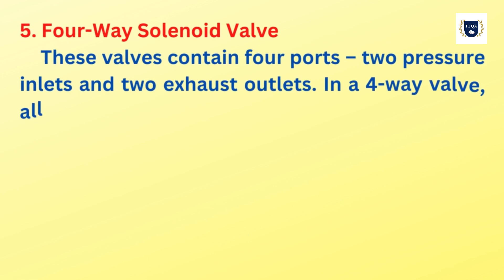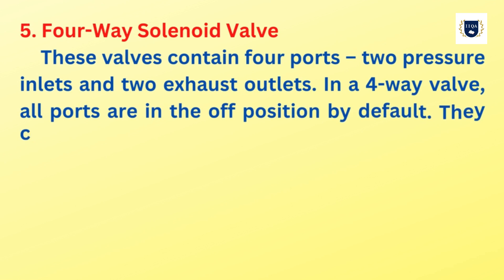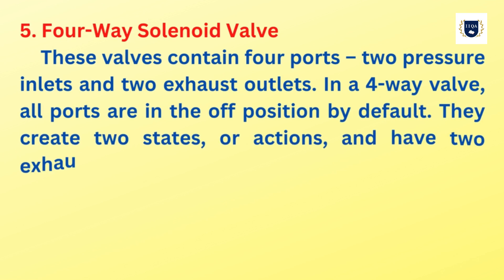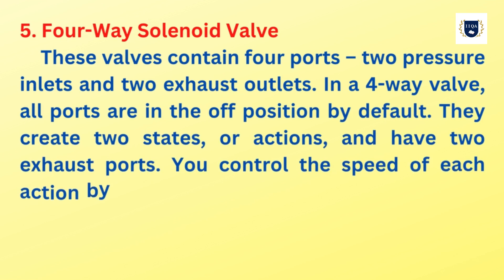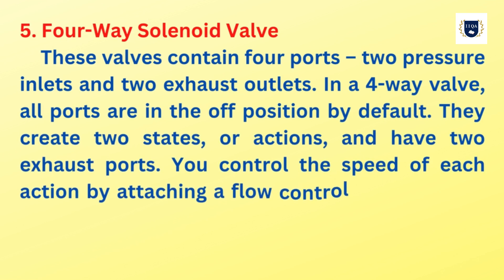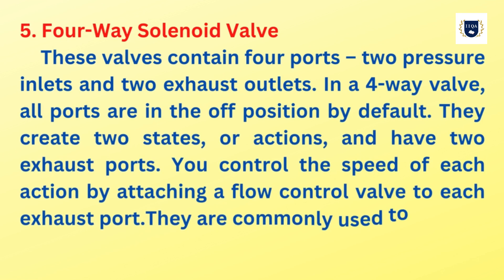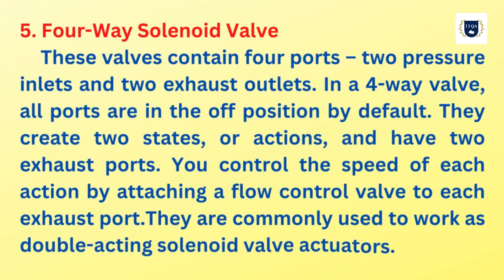Five, four-way solenoid valve. These valves contain four ports — two pressure inlets and two exhaust outlets. In a four-way valve, all ports are in the off position by default. They create two states or actions and have two exhaust ports. You control the speed of each action by attaching a flow control valve to each exhaust port. They are commonly used as double acting solenoid valve actuators.